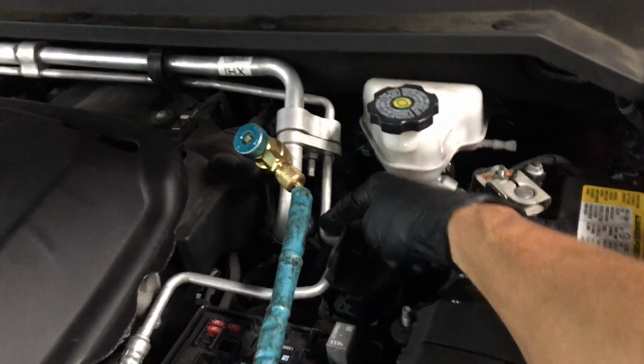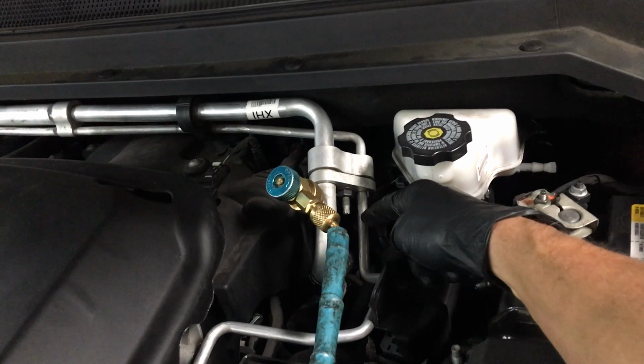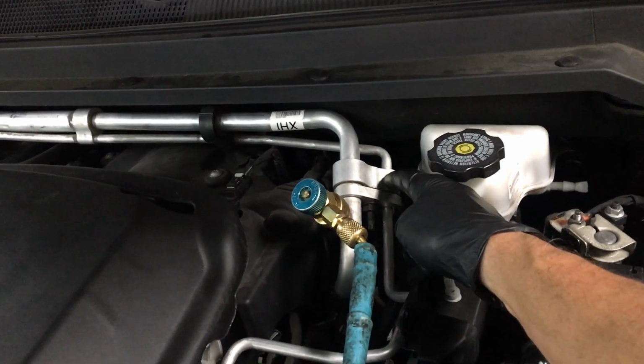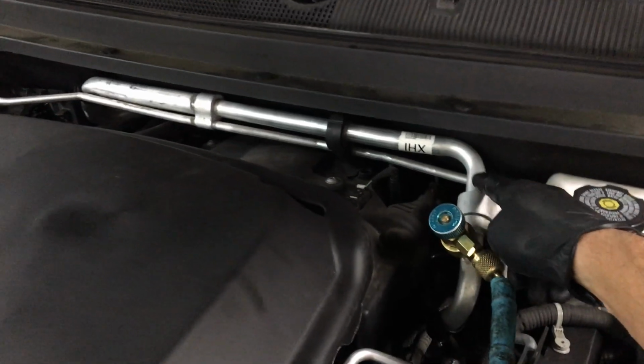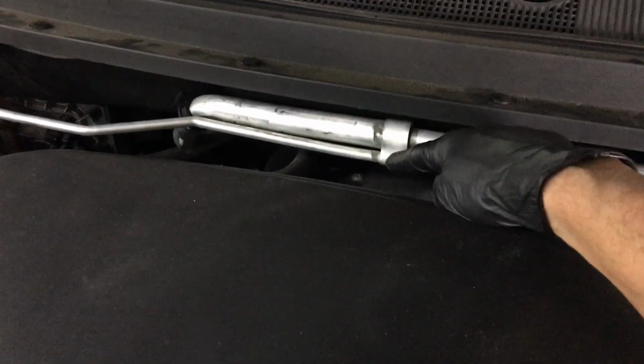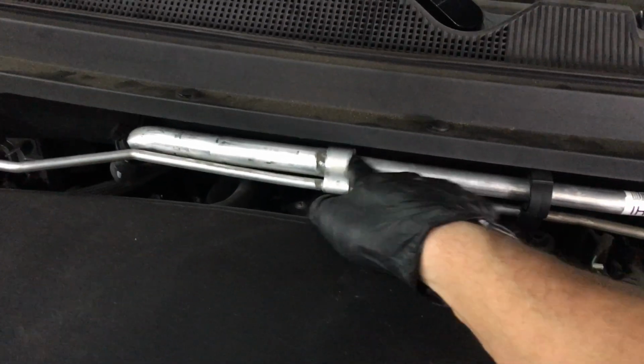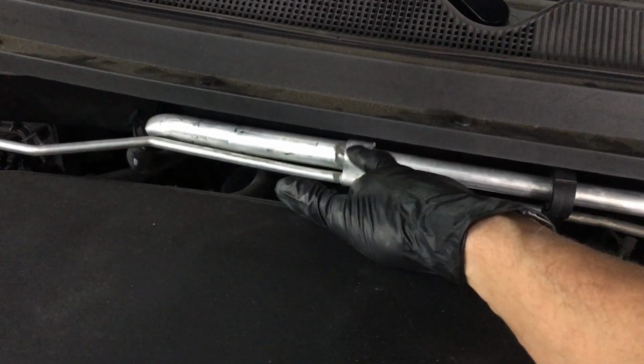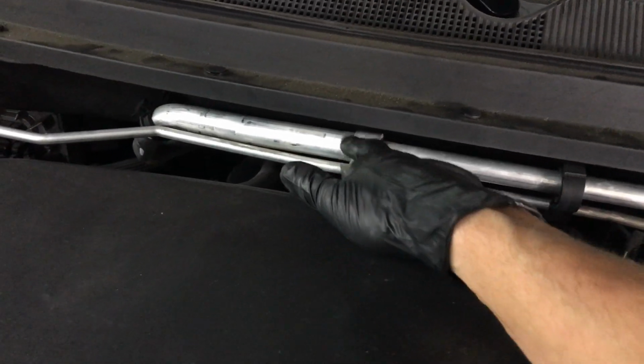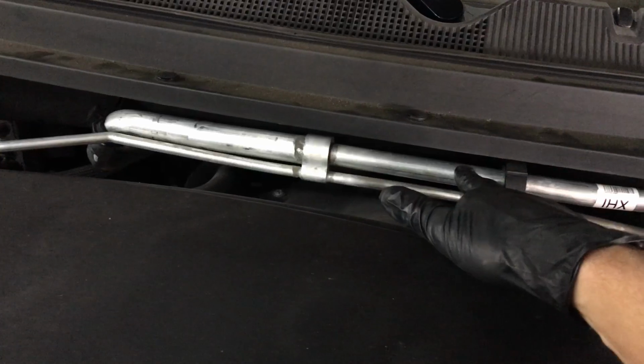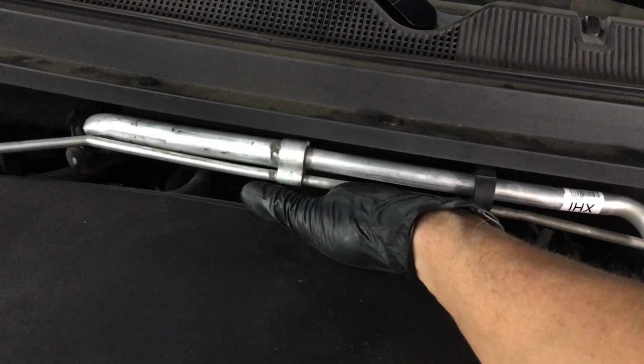Well, unlike the rest of the cars out on the market and HVAC guys who are just thinking regular residential split system, this has an internal heat exchanger where it's actually swapping a little bit of its cooling. If you see this liquid line right here, you see this suction line right here, well actually as it goes in here, there's a tube that goes from here up and around, or actually it's over here on this one. It goes here, up and around, and you see how this line is bigger than this line? Within this fitting, the liquid is actually traveling around this cold suction line, and the heat is being removed from the liquid. High pressure liquid refrigerant is being cooled through this internal heat exchanger right here.